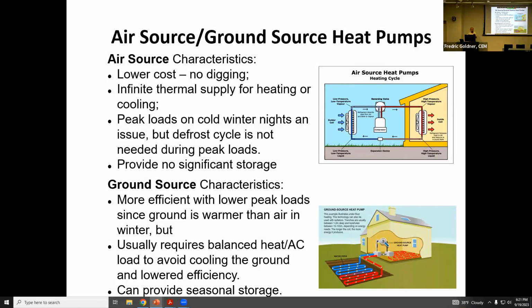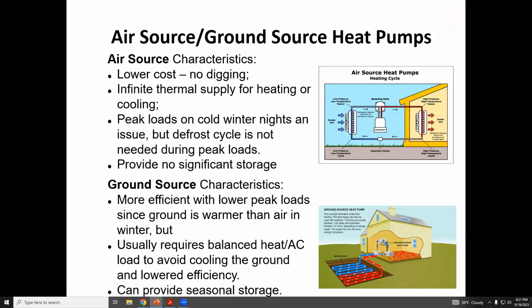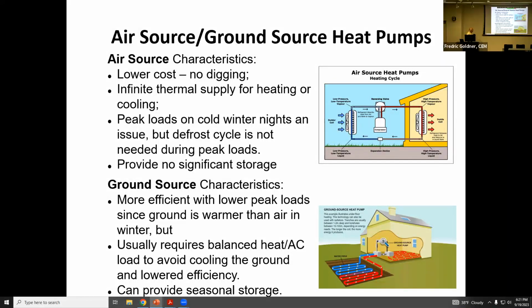You need the defrost cycle when the outside air is at 30, maybe 28, maybe 40, certainly 40, because that's when frost will build up on the coils. So the only thing you need for peak loads is the power that's actually running the compressor and moving the heat. But that is a substantial amount of power in the middle of winter.